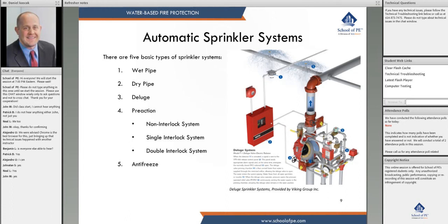The fifth system is somewhat archaic — the antifreeze system — where an antifreeze solution is mixed with the water to prevent freezing. It used to be common for small loading docks or small systems in freezing conditions below 40 gallons, where it was economical. However, the cost of dry pipe systems has gone down, making antifreeze no longer economical, and there are also environmental concerns with putting antifreeze on a fire.